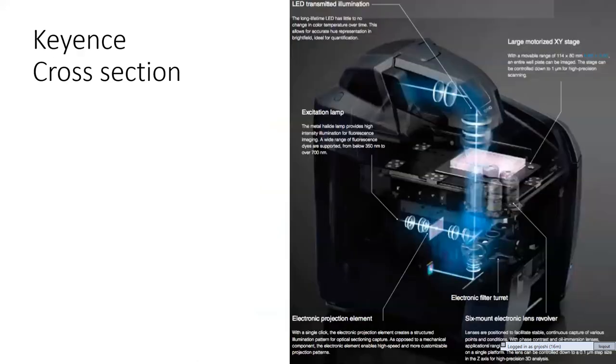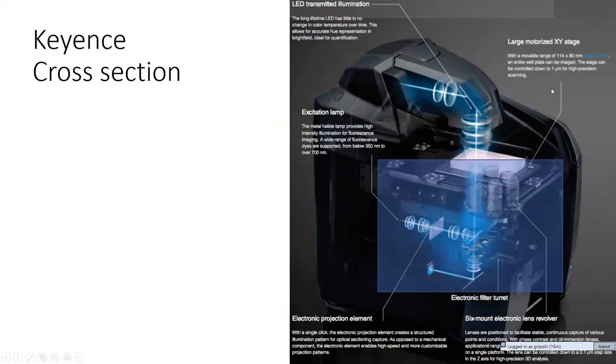Now, how does this relate to Keyence? If we look at the cross-section of Keyence, I will be focusing on the fluorescence part of the Keyence and not the transmitted light part. So if we look at the cross-section and just focus on this area, the first thing is we have an excitation source. The excitation source in Keyence is a metal halide lamp.